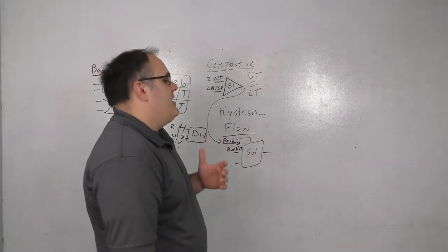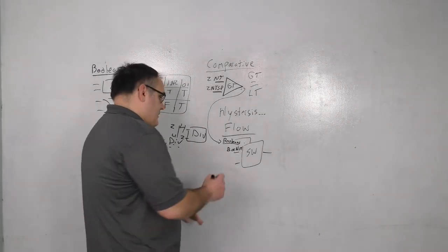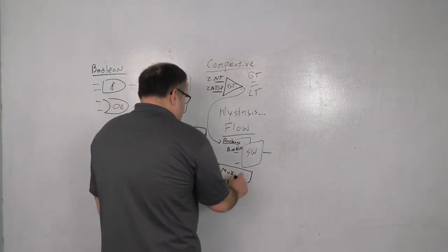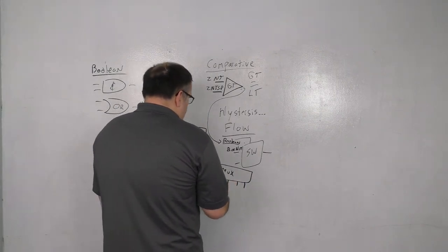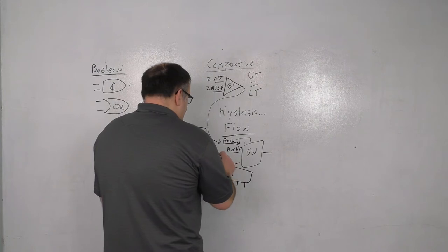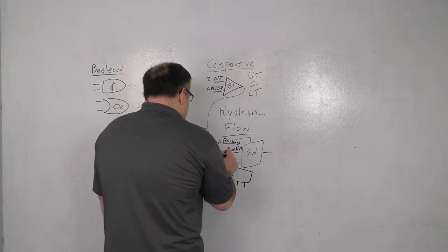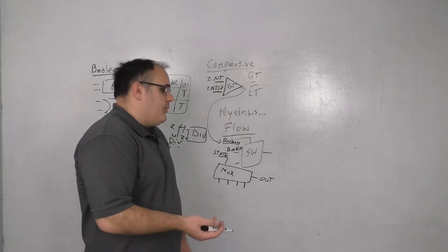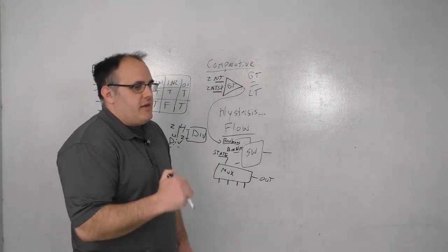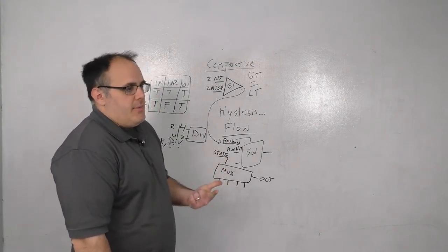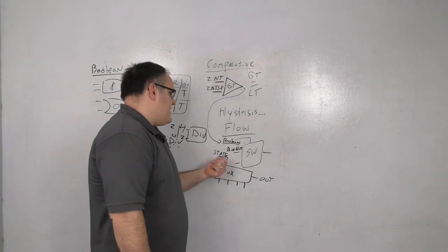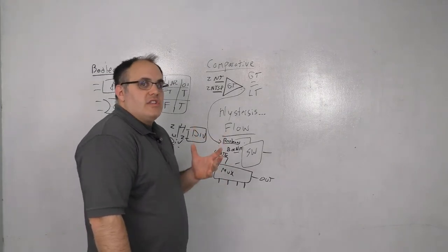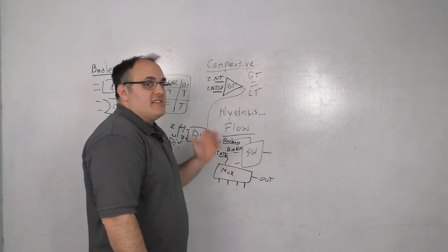The switch is awesome. Now, what's the difference between a switch and a multiplexer? A mux is like a switch, except it has states. So a multiplexer can take multiple different inputs, and based on a state trigger, can write multiple different output types. You'll see this in state machines, so stateful programming. A common stateful object would be an occupancy object where you have off, unoccupied, standby, and occupied. You would pass that 4-state object into a multiplexer, and that multiplexer could then drive 4 different logic states based on the state of that incoming object.